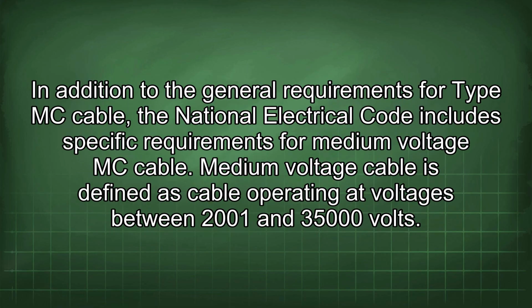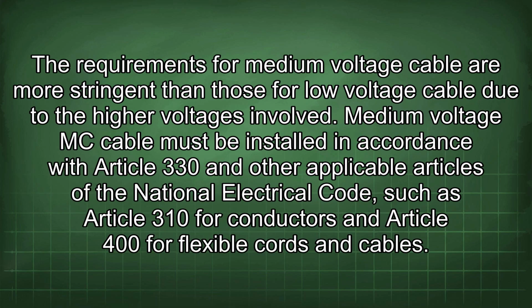In addition to the general requirements for Type MC cable, the National Electrical Code includes specific requirements for medium voltage MC cable. Medium voltage cable is defined as cable operating at voltages between 2001 and 35,000 volts. The requirements for medium voltage cable are more stringent than those for low voltage cable due to the higher voltages involved. Medium voltage MC cable must be installed in accordance with Article 330 and other applicable articles of the National Electrical Code, such as Article 310 for conductors and Article 400 for flexible cords and cables.